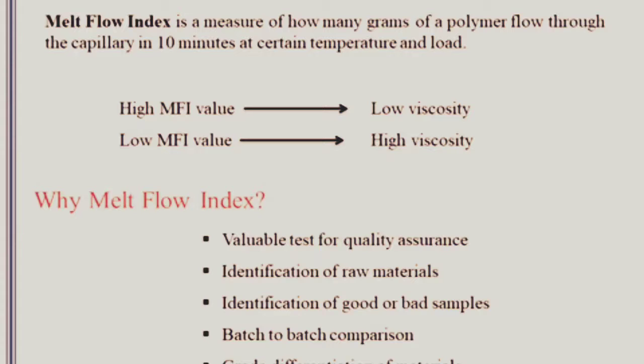Since MFI value can be directly related to viscosity of material, MFI is used as a basic tool for quality control. It also helps in identification of raw material, distinguishing good or bad samples, batch-to-batch comparison, and grade identification of materials. For example, if the lot of material you are processing has an MFI of 10 and a new lot has an MFI of 15, you can anticipate issues such as flash, over packing, and overweight product, and make the appropriate adjustments accordingly.